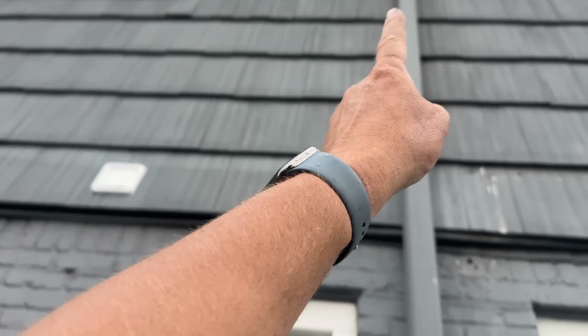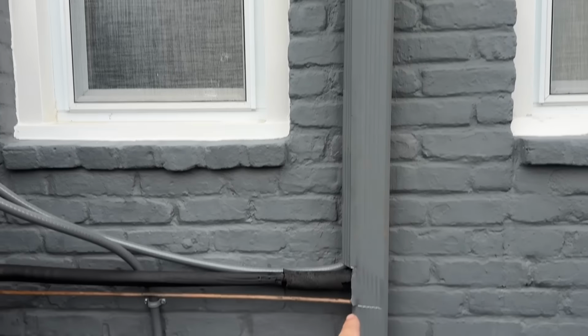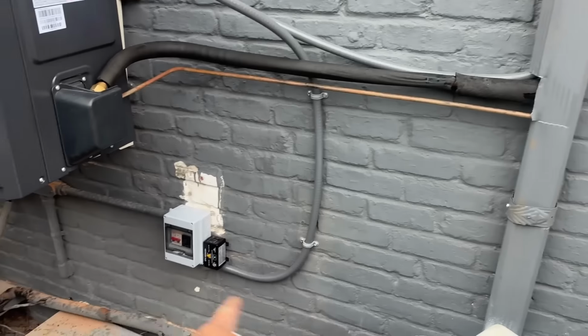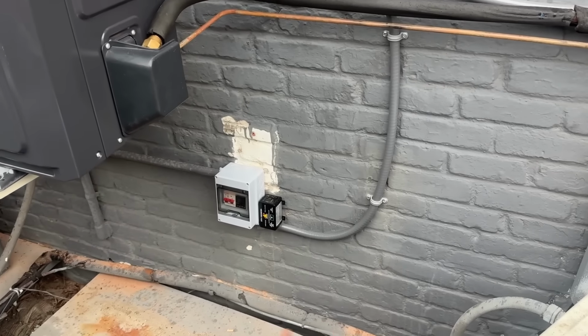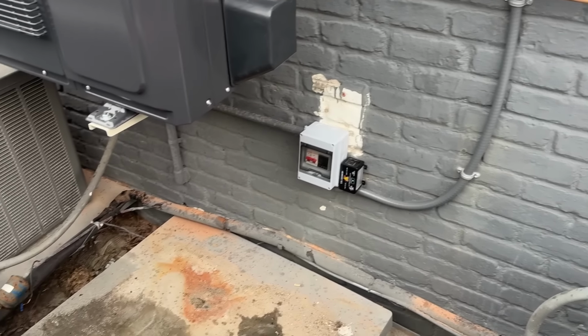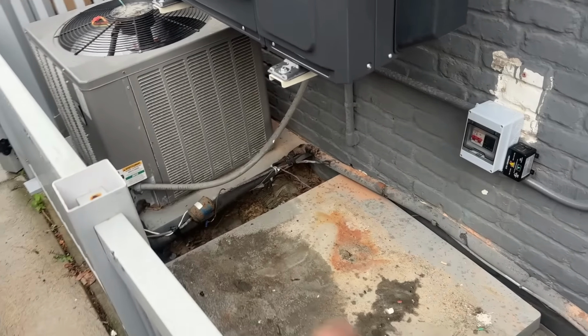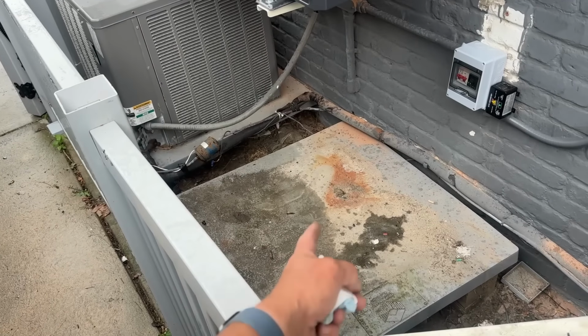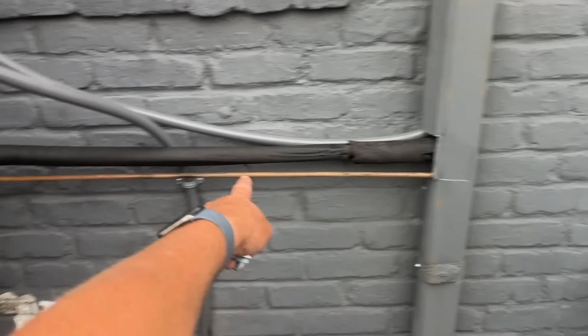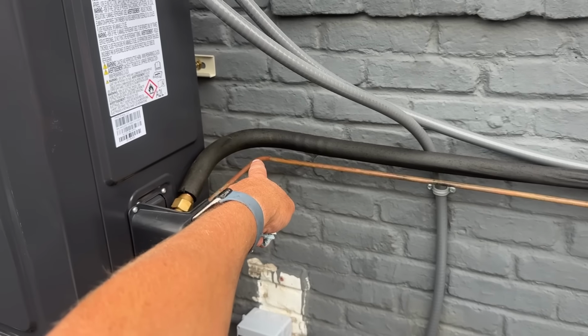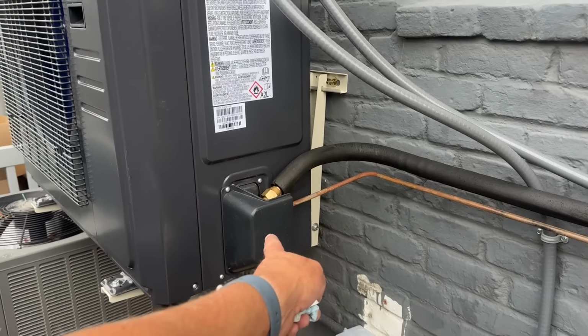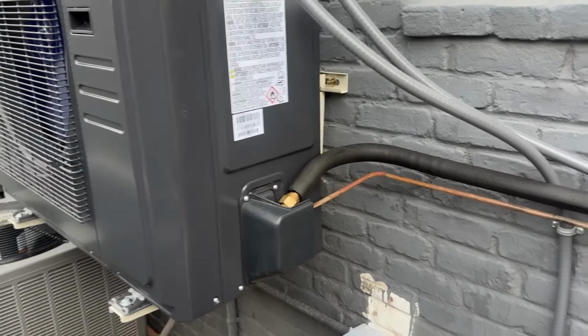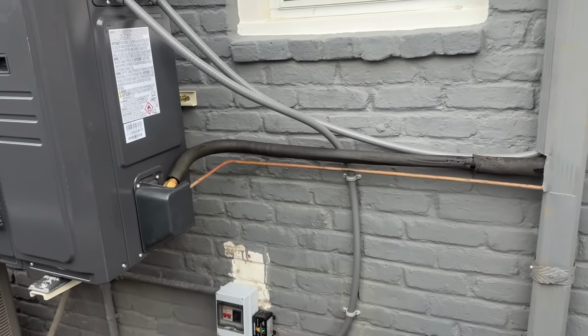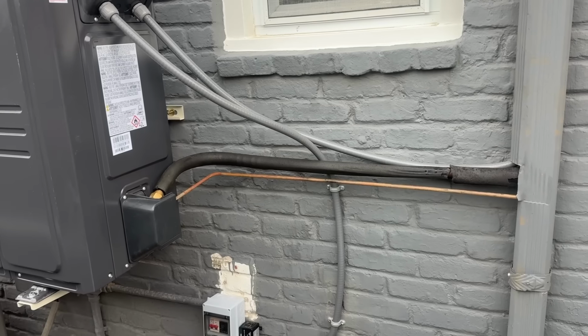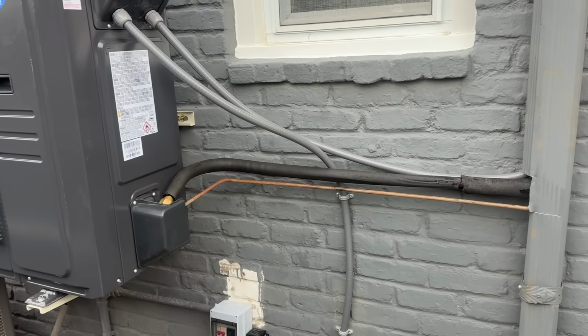Our line set was 3/4, then it went to 7/8, and there's couplings, swedges that didn't exist. A 90, another coupling, went to our outdoor condensing unit, which sat on this pad right here. 3/8, put a nice little bend right there, went straight across. 90-degree turn in there, and a little kick right there to our flare joint. There was no use of torch during any part of this job, reducing the risk of carbon buildup on the inside of the piping.